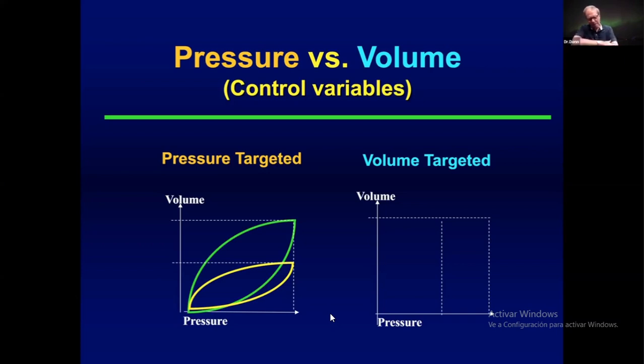And this is what happens if you keep the pressure constant and you change the compliance. So the green loop represents what might happen after the administration of surfactant. And now at the same pressure, we're delivering quite a bit more volume. The converse is also true. So if the green breath were our index breath and the baby suddenly developed a diminished compliance, maybe a pneumothorax, maybe pulmonary edema, anything that limits compliance, at the same degree of delivered pressure, we're now going to deliver a lot less volume to that baby.